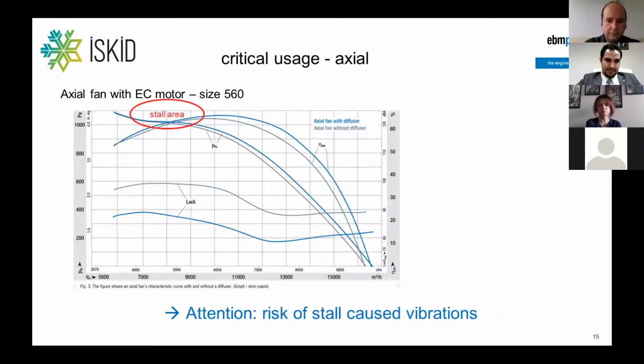Axial fans, for example, have a certain area which is dangerous for the installation. They have a stall area which is quite close to the maximum efficiency. So there are some risks in that, because stall creates pressure shocks in the air handling unit, and this may cause mechanical damage and vibrations.